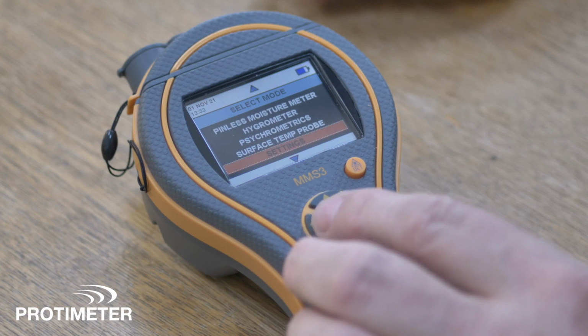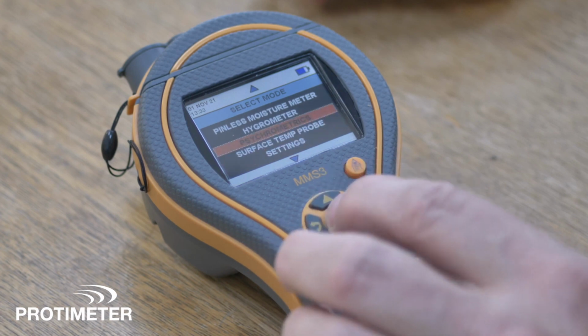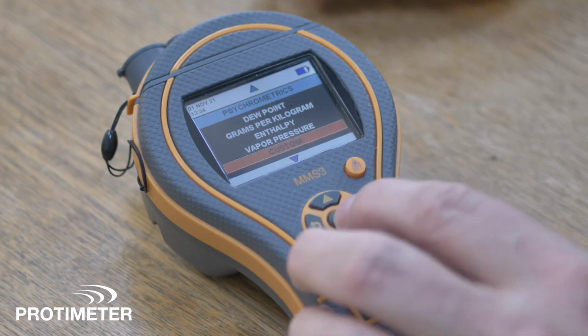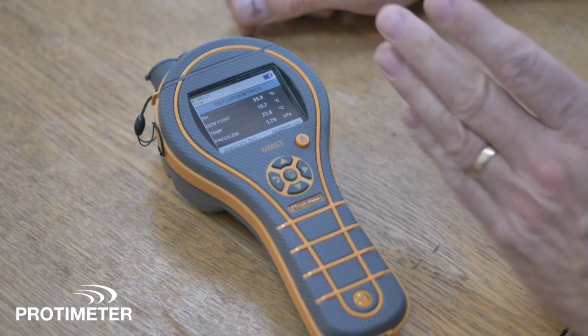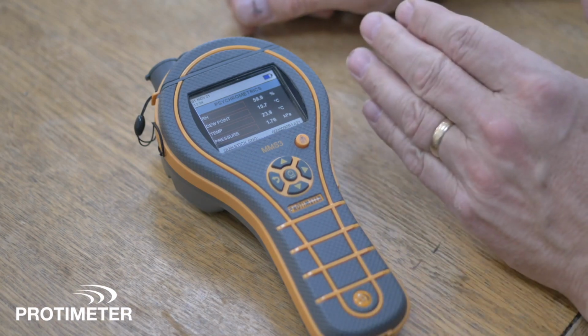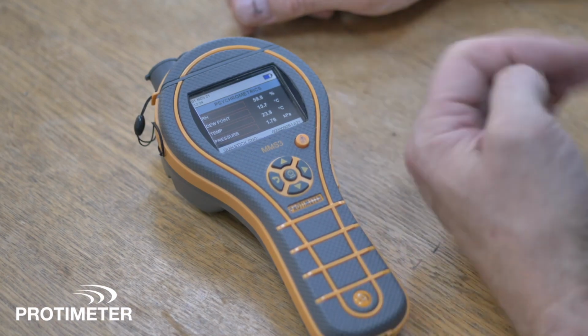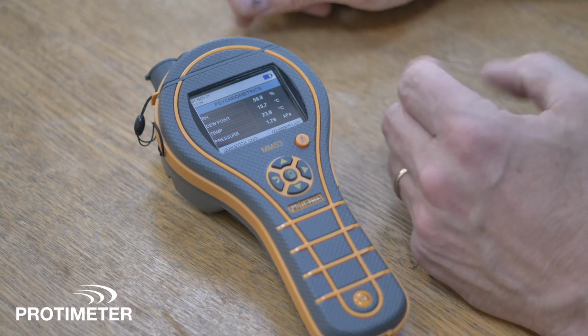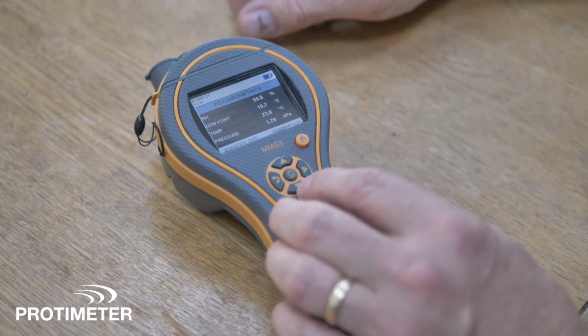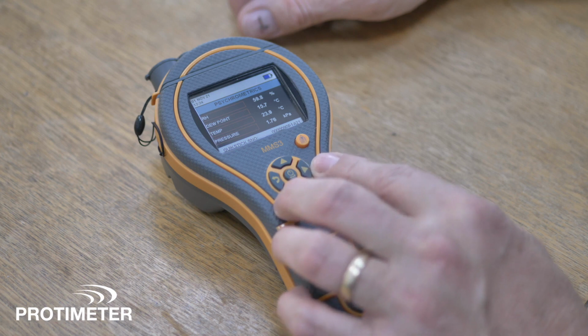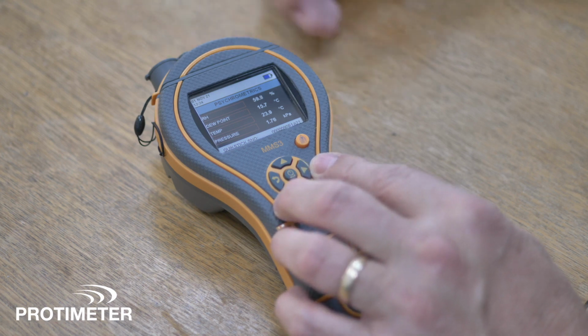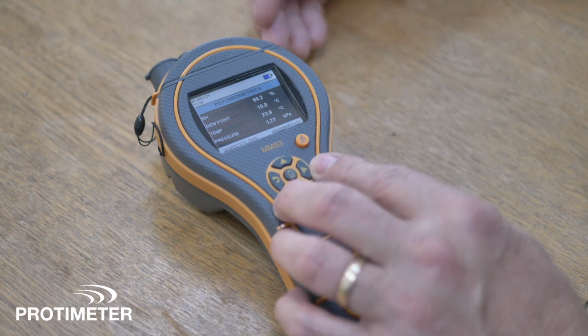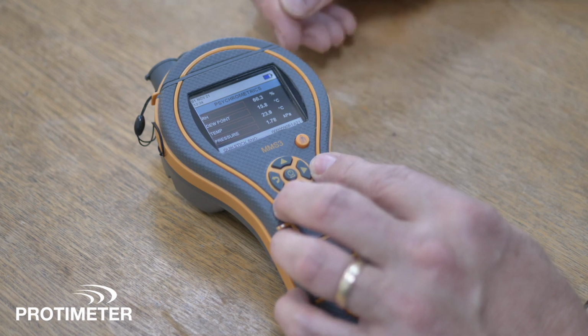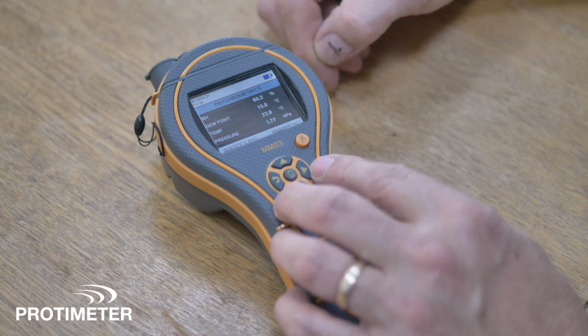Now let's go back to our custom mode in psychrometrics, and you'll see all 4 of those readings in the order you selected them. This is really handy instead of changing between functions to see all the readings you might want to record. These can be saved in the internal memory, as can any reading from any function of the meter, and also transmitted to the app for data recording.